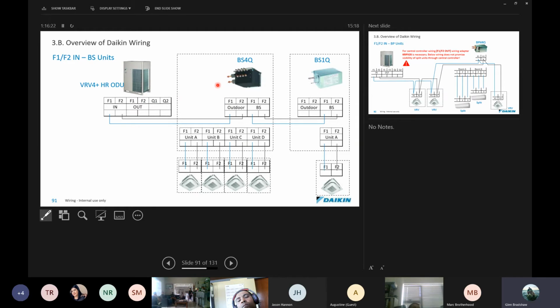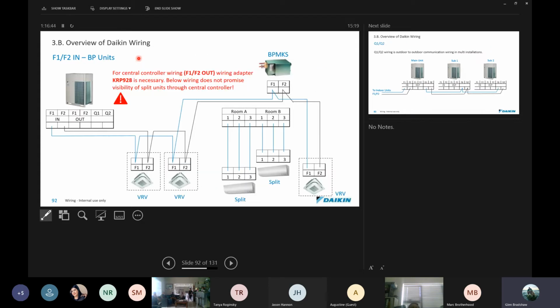It's quite something to try and reset, because once the system codes up, it has addressed everything inside the system, and it takes a hard reset of about 45 seconds to undo this. We've had cases where it hasn't been undone, and we've actually had to replace the PC board and the condenser. And it's not a warranty claim if it's a wiring fault. The same thing can happen with BP boxes. You've also got A, B, and C ports on them, and from time to time we found that these are being swapped around as well. So take note when you're installing, have a plan, make sure that your piping is accounted for on one port and that the wiring for that port travels with that piping as well.